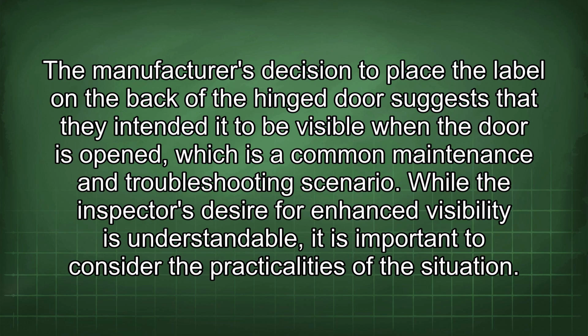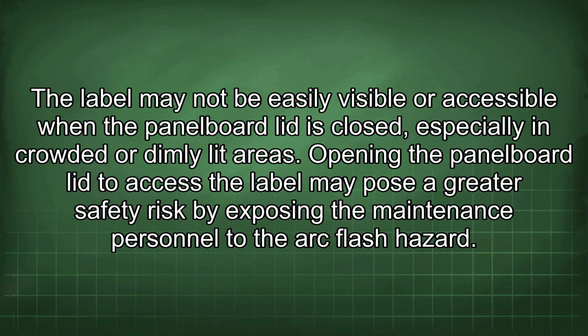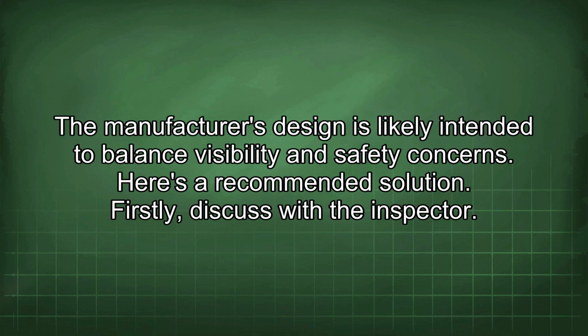While the inspector's desire for enhanced visibility is understandable, it is important to consider the practicalities of the situation. The label may not be easily visible or accessible when the panel board lid is closed, especially in crowded or dimly lit areas. Opening the panel board lid to access the label may pose a greater safety risk by exposing the maintenance personnel to the arc flash hazard. The manufacturer's design is likely intended to balance visibility and safety concerns.